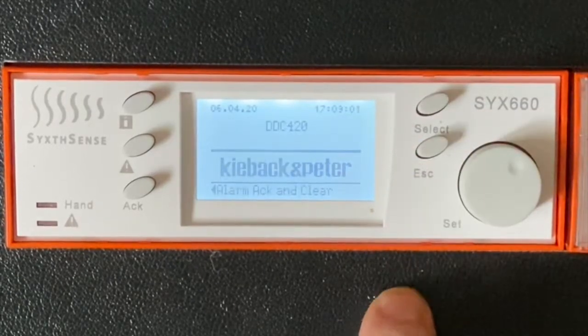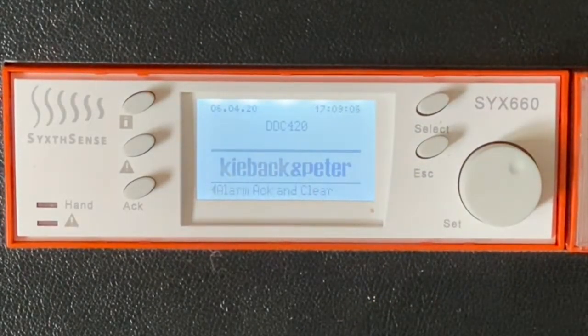Another nice feature of the SYX controller is the commissioning mode. Now, it's a common factor that a lot of heating controllers are installed during the summer months. This is where the plant is of no use, is in a maintainable state, should we say. So during the summer months, most of the boiler houses are being refurbished or controls are being upgraded. So during those summer months, it's the last time of the year where we actually want to have the heating running. So we have to find a way of making the plant work so we can actually test the plant. So having the commissioning mode is really, really handy, because we don't have to over manipulate the controller to make it operate, because a heating controller will fight us trying to make it run in summertime.